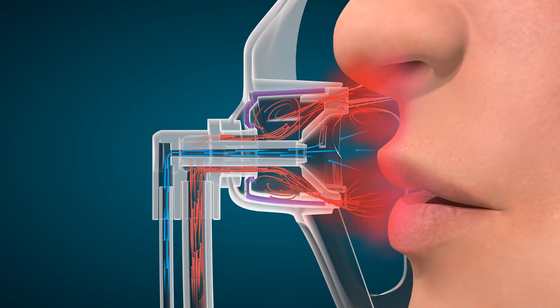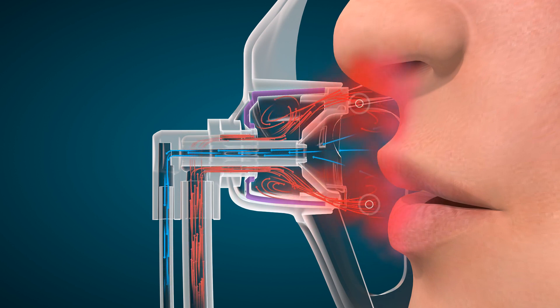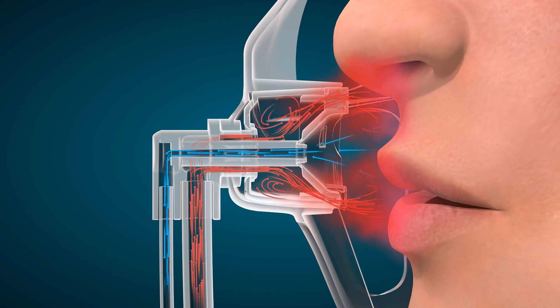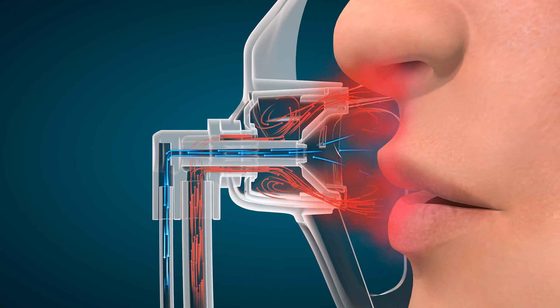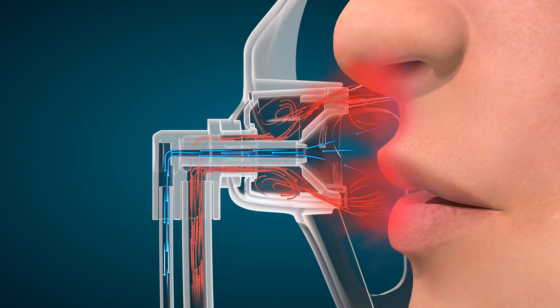The triangular directional diffuser refines the shape of the oxygen vortices and accelerates the flow toward the patient's nose and mouth. These redesigned directional ports and mushroom-cupped disc also allow for improved capture of end-tidal carbon dioxide into the CO2 sampling line, even at higher flows of oxygen.